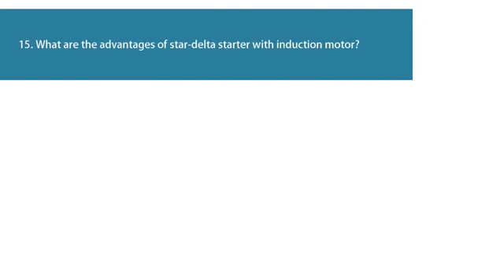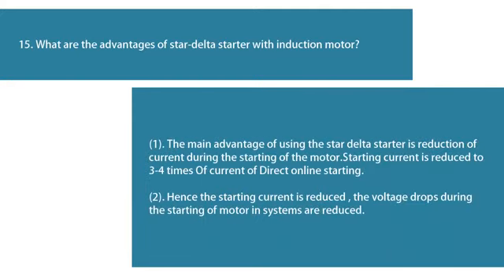Question 15: What are the advantages of a star-delta starter with an induction motor? The main advantage of using the star-delta starter is reduction of current during the starting of the motor. Starting current is reduced to three to four times less than direct on-line starting. Hence, the voltage drops during the starting of the motor in systems are also reduced.